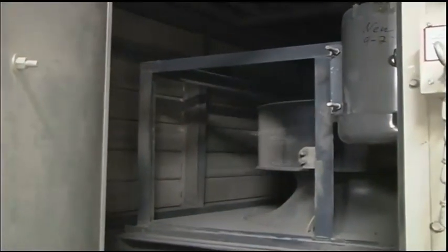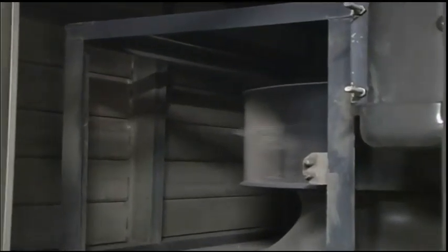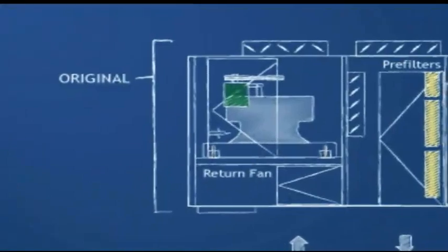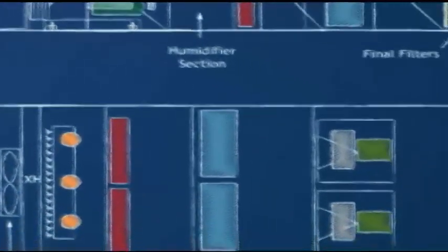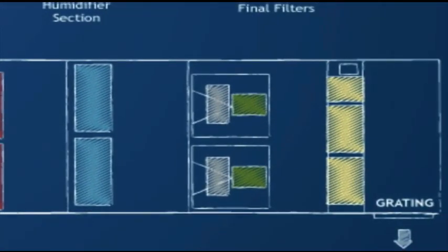A second concern was the reliance on a single belt-driven fan and motor for these critical patient service areas. With advice from HuntAir, they decided to convert the air handler from a blow-through to a draw-through design, and to replace the single fan with a four-unit fan wall array.